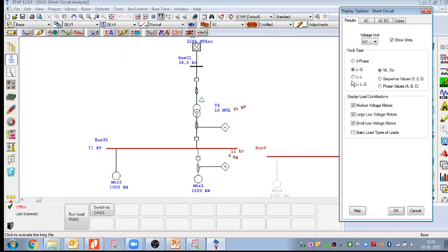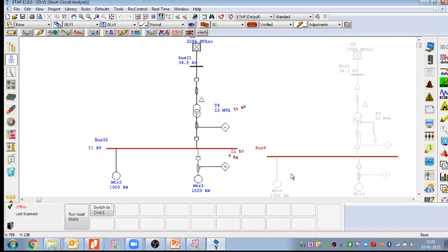Yes, the three phase fault we have already seen. Now the fault type L2G. I am taking the display short circuit current fault type. These are the fault types, as we know. Now I have taken the line to ground fault type. Click on OK. The value is 0 kiloampere.